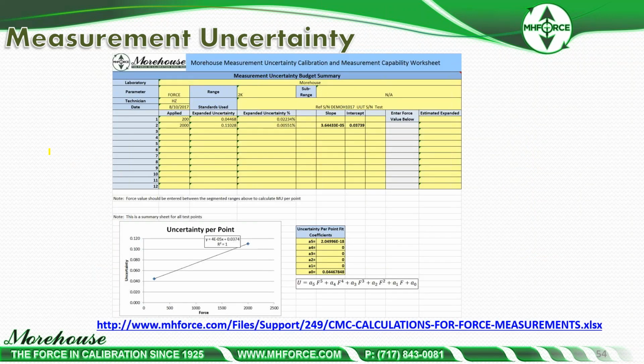Here's another good example, back to the lab that claims 0.05% of full scale. This is with one load cell, not two. This is in our PCM. This was controlled. This was done for a class where we had people in class and we took the results. Every time we do this, it comes out a little different. The one at the top, not so much. So at the top, I can claim 0.005% of full scale.